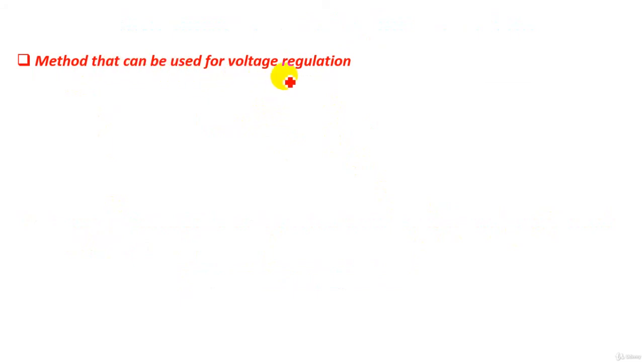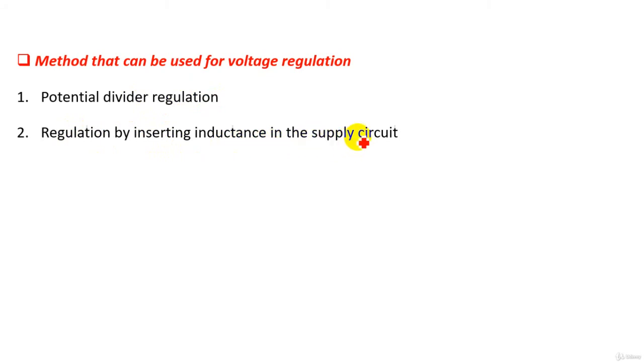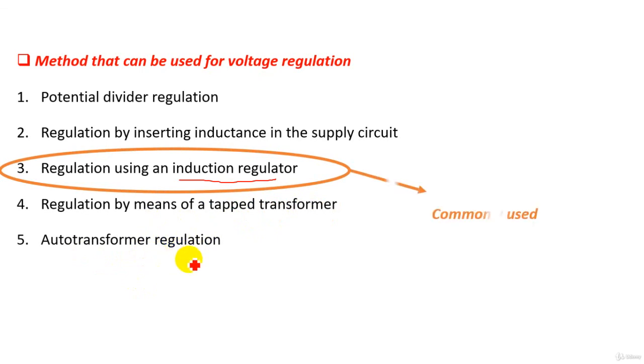There are many methods that can be used for voltage regulation. The first is potential divider regulation, based on the principle of the potential divider using two or multiple resistors. The second is regulation by inserting inductance in the supply circuit. Third is regulation using an induction regulator. Fourth is regulation by means of a tap transformer, using transformer taps to obtain variable voltage. Fifth is auto transformer regulation. The induction regulator is the most commonly used method, as it can provide smooth variation of voltage and is also compact and small in size.